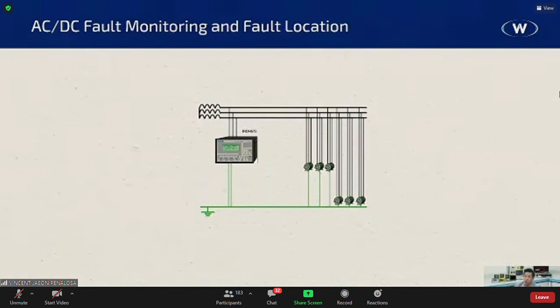So if you had two insulation monitoring devices in one IT system, then either one of the devices will measure the other one as a fault. Okay, so you only need one. All right, so there you have an insulation monitoring device. Now, let's say we encountered a fault right here. What will the system tell us? The system will immediately tell us that you have an insulation fault and will give us an insulation reading, right? And right now, measuring in true RMS, it tells us it's already at 10 kilo ohms. If you remember the things we have to do whenever we have insulation faults: number one, detection; number two, location; and number three, elimination. Problem number one, detection, solved, because we already know that we have a problem.